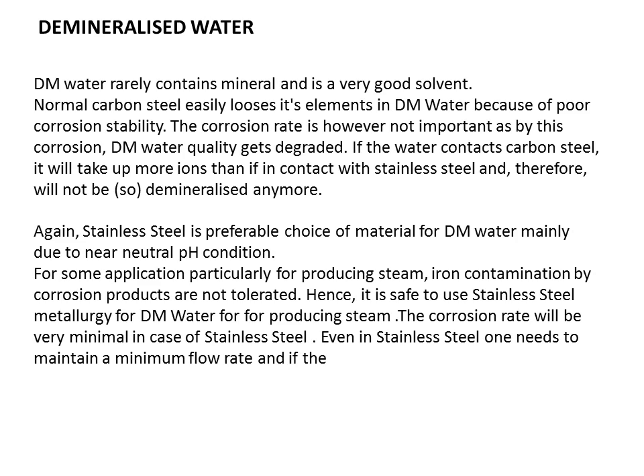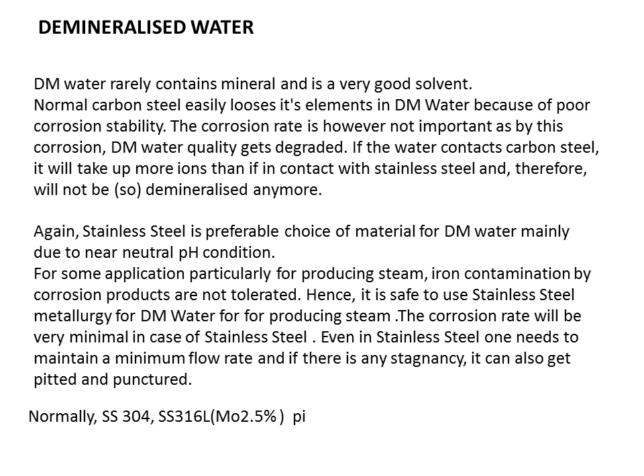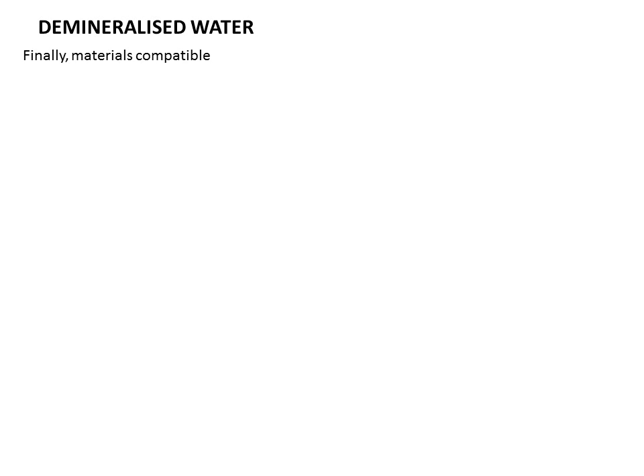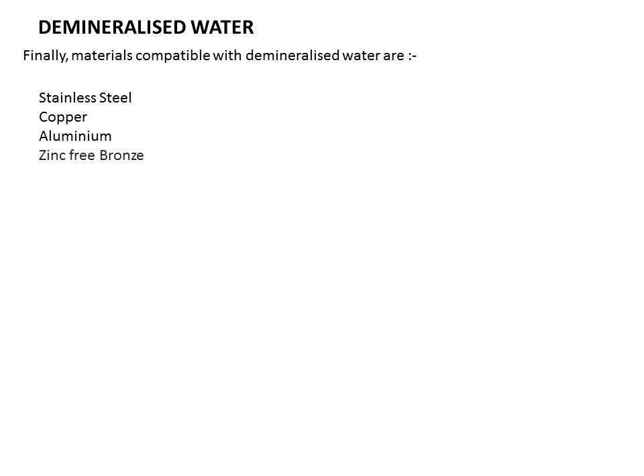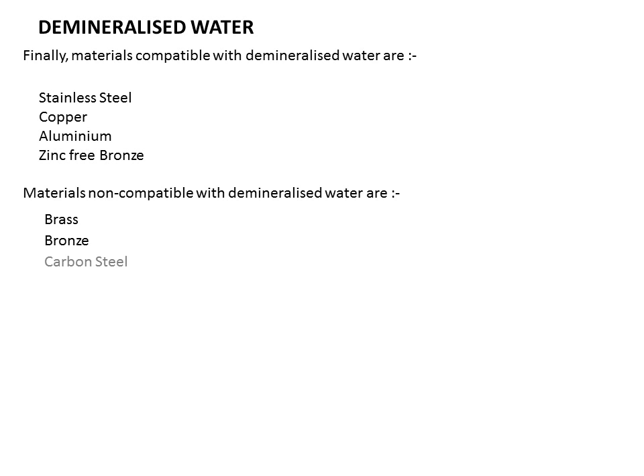Even with stainless steel, one needs to maintain a minimum flow rate; any stagnancy can cause pitting and puncturing. Normally, SS304 and SS316L containing molybdenum (~2.5%) are used for demineralized water. Materials compatible with demineralized water are stainless steel, copper, aluminium, and zinc-free bronze. Materials non-compatible with demineralized water are brass, bronze, carbon steel, galvanized steel, and chromate steel.